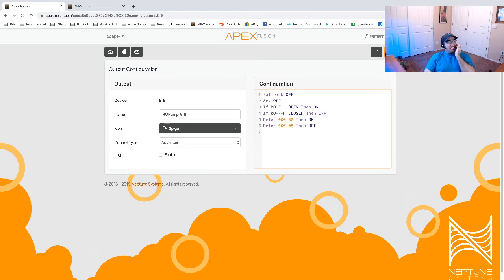So Ravi, that's how you do it. You need a low and a high, and it's quite simple. When the low sensor recognizes there's no more water, it turns on, and it stays on until it gets up to the high sensor, which closes and turns it off. So write this down — I don't know what your high and low sensors are, but that's how you would do it.